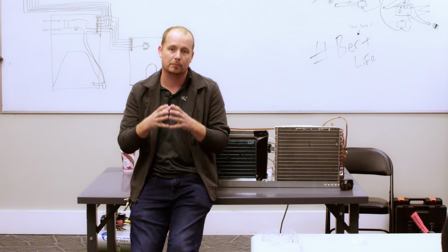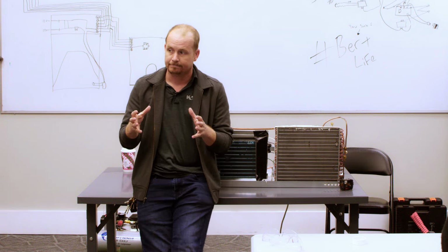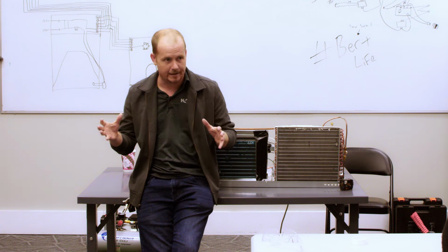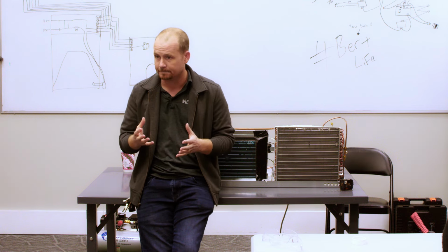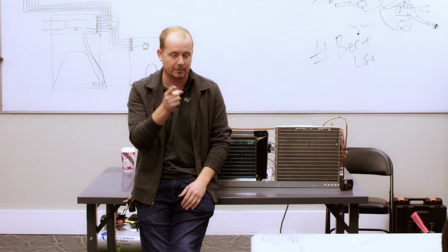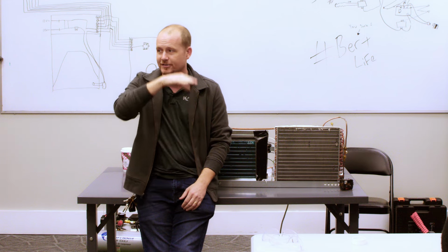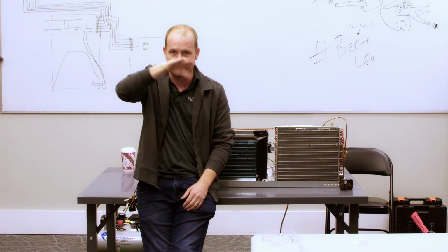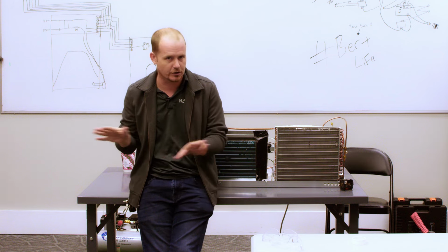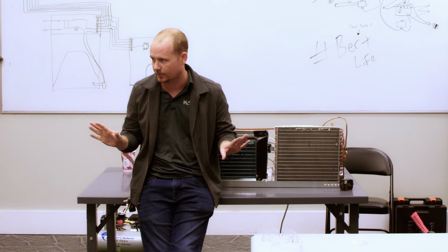And this is where that term approach comes in. It's not a measurement you guys take a lot. If you've used MeasureQuick, you'll see it on there. But approach is just comparing your liquid line temperature to your outdoor temperature. That's all it is. Now, approach is tricky because it's on a curve. You can hit approach two different ways, and that's why we don't just charge to approach. I'm not telling you to just charge to approach.